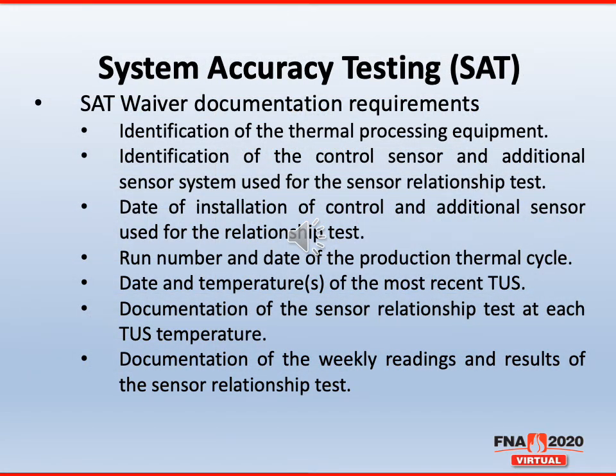We also added some documentation requirements when you are conducting the SAT waiver. Again, the previous revision didn't give you any guidance on how to document this, but now there are new requirements for the documentation. Again, identification of the thermal processing equipment that you're conducting the waiver on, identification of the control sensor and that additional sensor system used for the sensor relationship test, the date of the installation of your control and additional sensor that's being used for the relationship test. You also have to denote the run number and date of the production thermal cycle when you do your weekly comparison check, date and temperatures of the most recent TUS, documentation of the sensor relationship test at each TUS temperature, and documentation of weekly readings and the results of the sensor relationship test. Again, some new requirements that have not been introduced until Rev F.